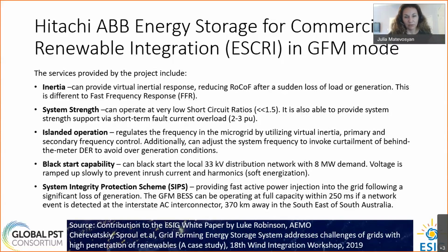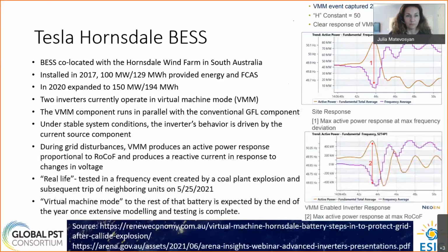Here the battery can inject full capacity within 250 milliseconds if a network event is detected and the AC interconnector from South Australia to the rest of the grid is tripped. So it's basically like a special protection scheme where the battery would provide fast frequency response. So as I mentioned, for this it wouldn't have to be grid forming, but just to mention that this battery provides this service.